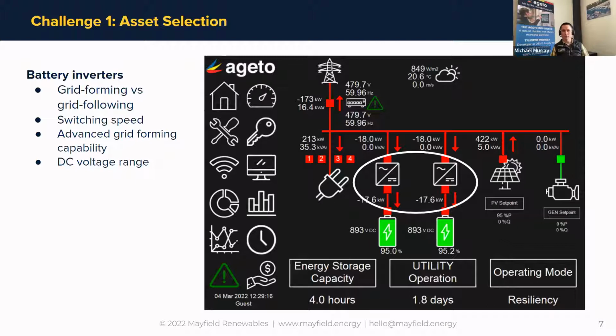And then there's the practical stuff on the integration. You want to make sure that the battery inverter and the battery DC voltage ranges match up, and that you have 480 volt 3-phase output or single phase, whatever the site needs. So those are the main things that I look for in energy storage inverters for microgrids.